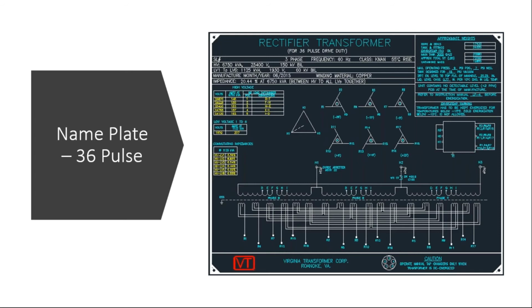You see the connections at the bottom, it says R1, R2, R3. It has 18 bushings, and in each phase you have 6 of them, one for each secondary winding. This is an extended delta configuration, where the portion outside the delta is for a different current, and the portion inside the winding delta is different. So the winding construction is kind of complex in terms of lead takeout and everything. Otherwise, the HV side is standard. It comes with the standard DETC or offload requirements. In this case, it was a 6.7 MVA rectifier transformer for a 36 pulse drive duty application.